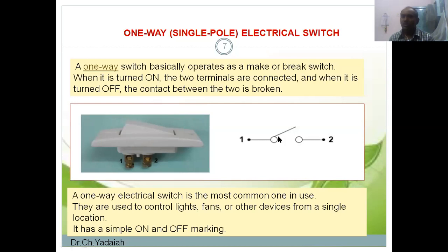So when the switch goes from closed position to open position in a fraction of a second, when the gap is very small, the air between the two contacts cannot oppose the flow of electrons. The electrons try to flow through this small area. Due to this, an arc may occur. That arc is handled by different methods in the case of circuit breakers.